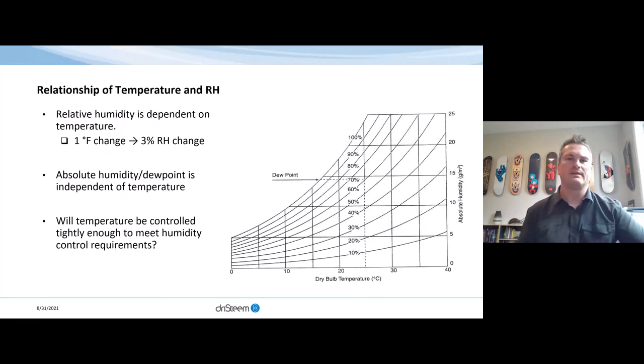So the relationship of temperature and relative humidity also impacts the percentages by very small amounts. One degree of temperature change can affect the relative humidity by as much as 3%. Absolute humidity and dew point are independent of the relationship relative humidity and temperature have. So controlling the temperature within the environment is really just as important as controlling the humidity level.